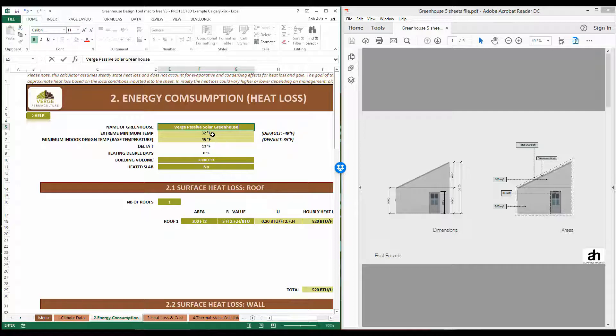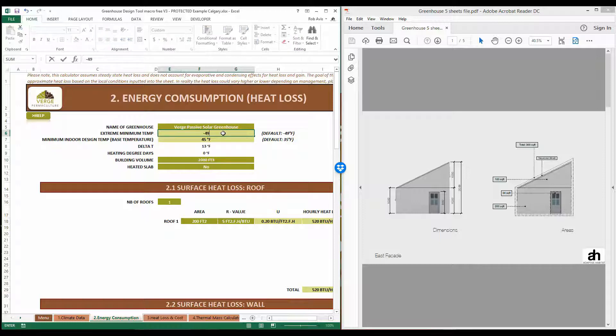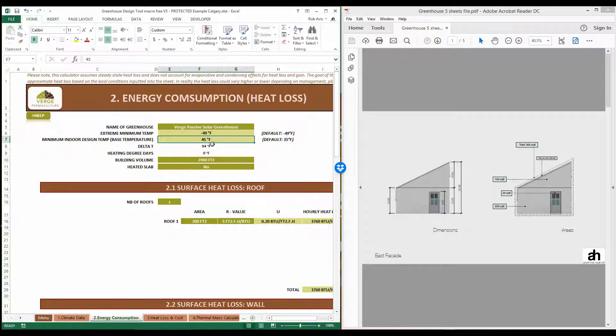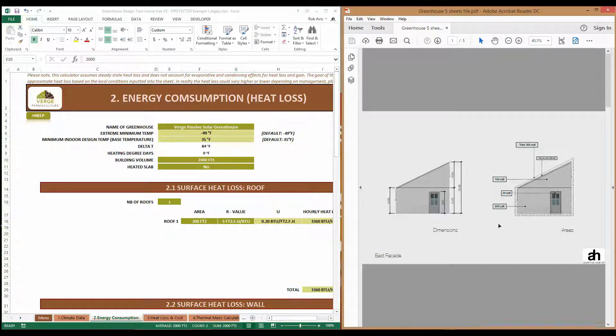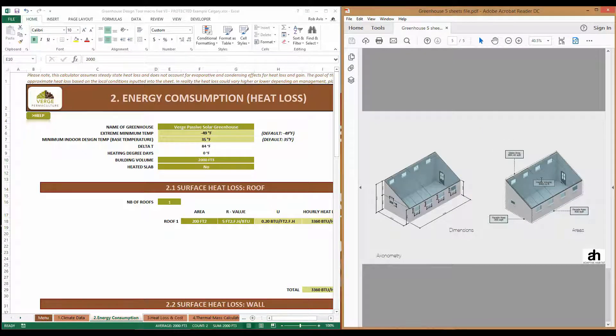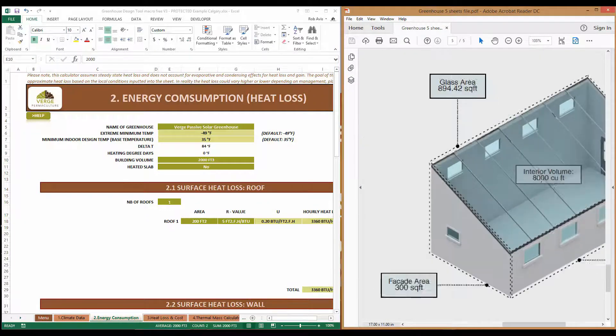Next, we need to enter the extreme minimum temperature. Notice the default number is populated from the climate sheet that we just entered. We also need to enter the minimum indoor design temperature, or base temperature, and it is 35 degrees Fahrenheit. The next piece of information we need is the interior volume of the greenhouse — in our illustration, this greenhouse had an interior volume of 8,000 cubic feet.